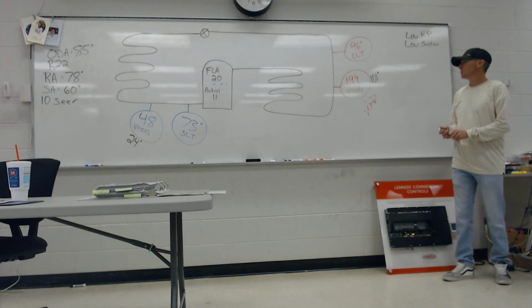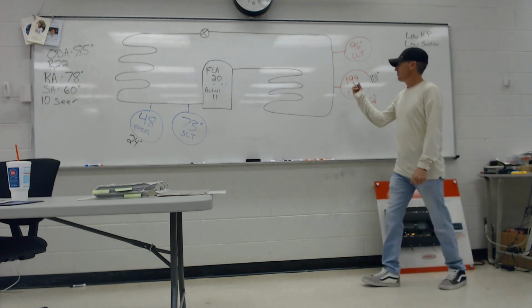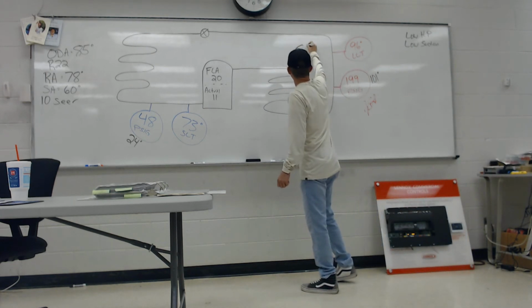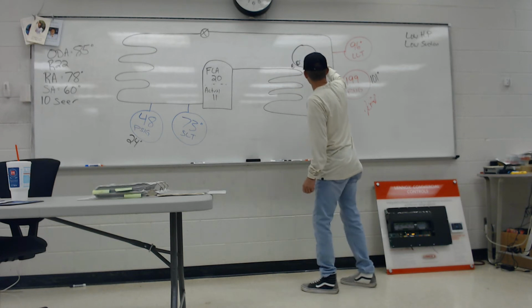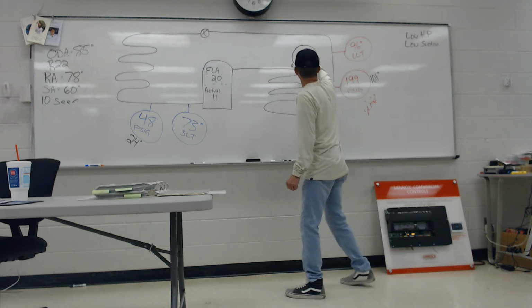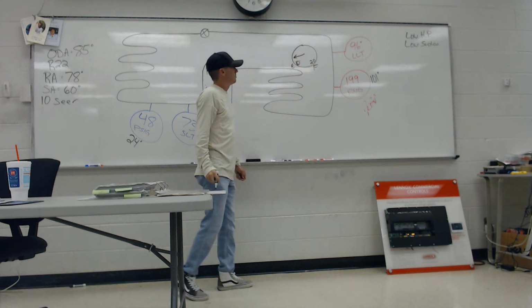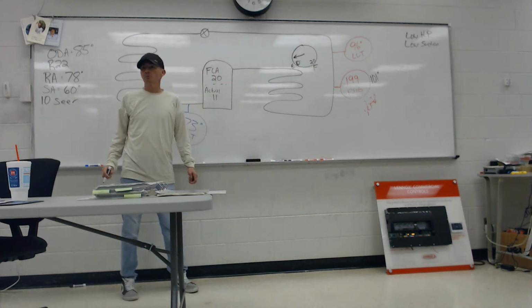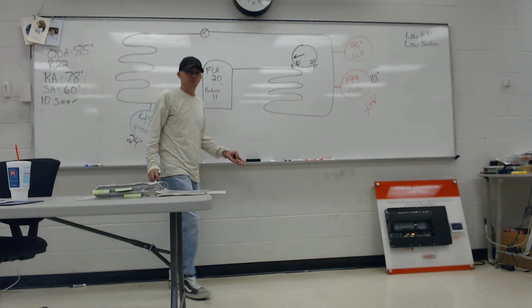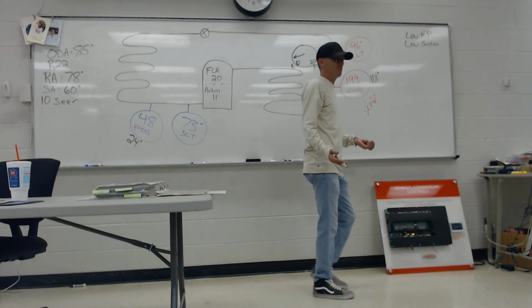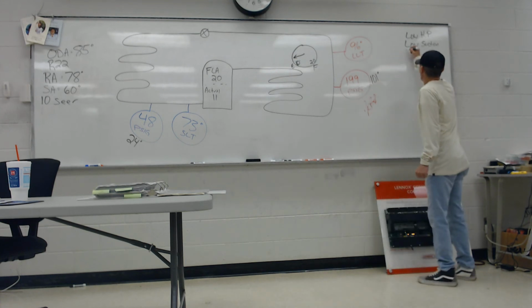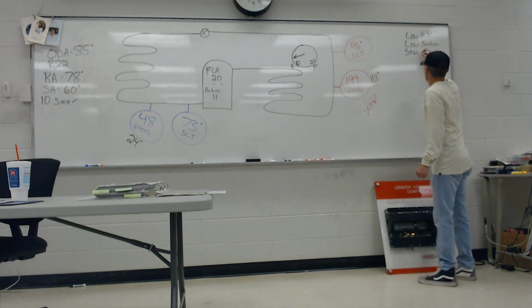Low subcooling. And remember, over here we've got the fuel gauge: empty would be 0 degrees, full would be like 20 degrees or something. I'm at 5 degrees, so you're starving. I've got a starved condenser. It's not crazy starved, but it's 5 degrees and we're looking for 10. Everybody agree with that?